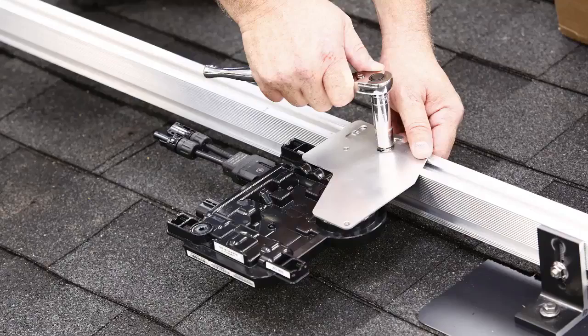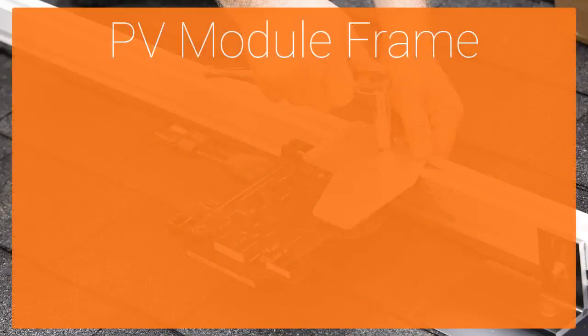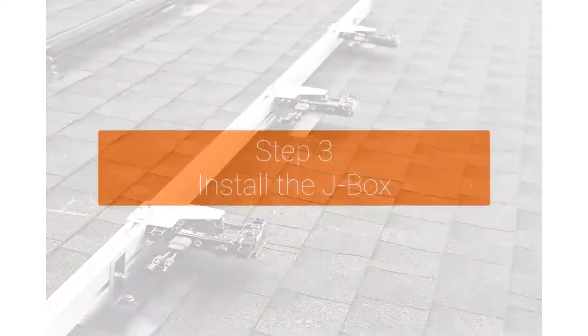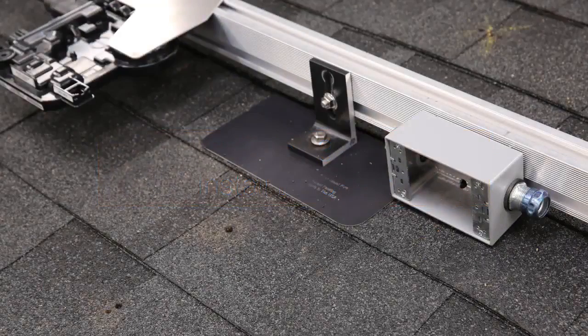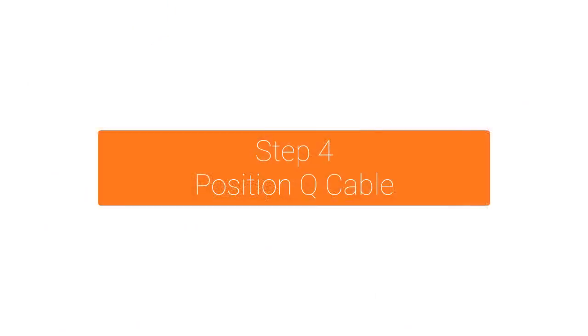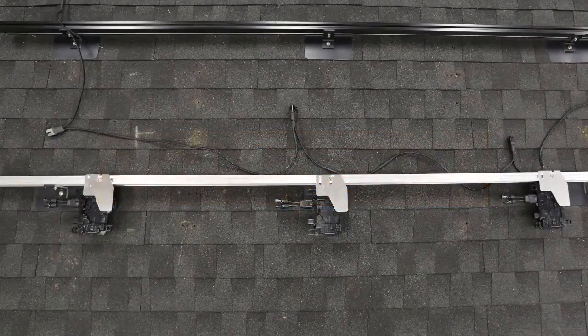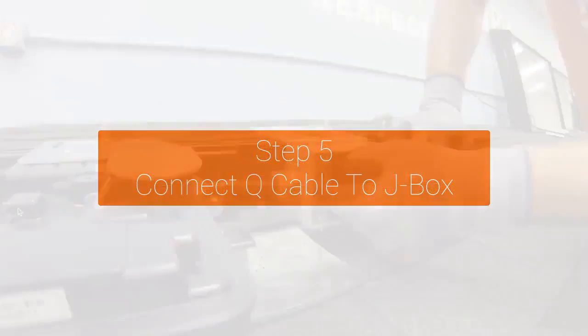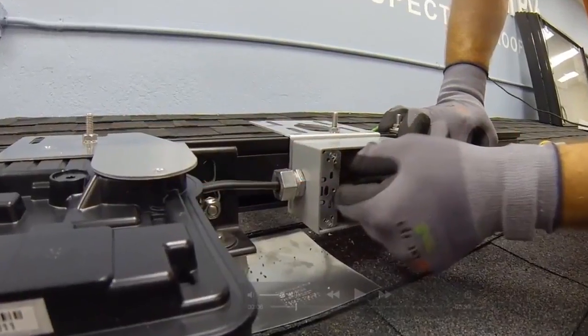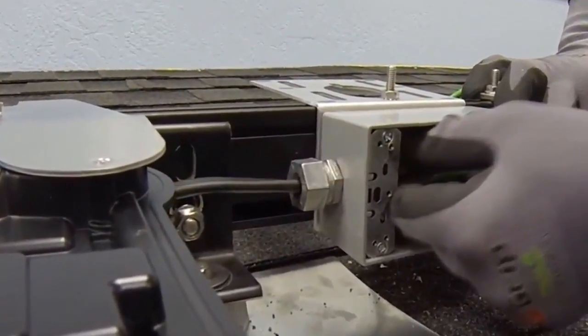When installing the microinverters, you should be mindful of obstructions, such as the PV module frame, module junction box, or circuit junction boxes. Install the junction box in a suitable location on the racking, in reach of your Q cable. Rough in the cable so that it aligns with the inverter position. Route the Q cable into the junction box using UF-type cable glands and complete all downrun AC connections.